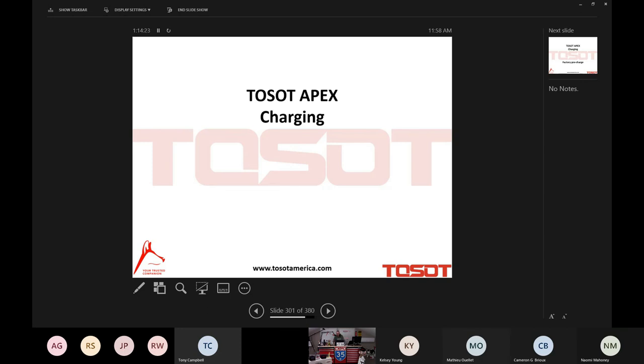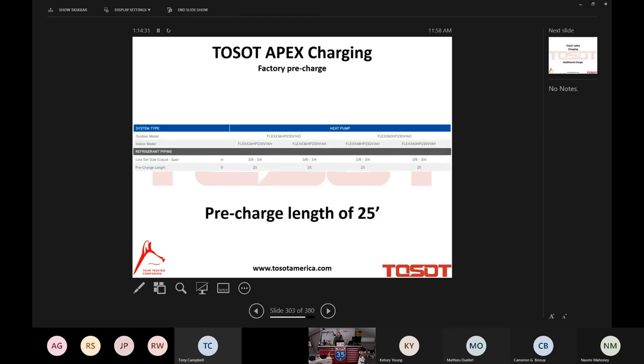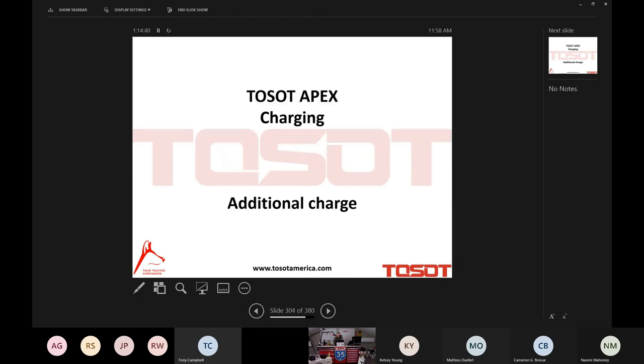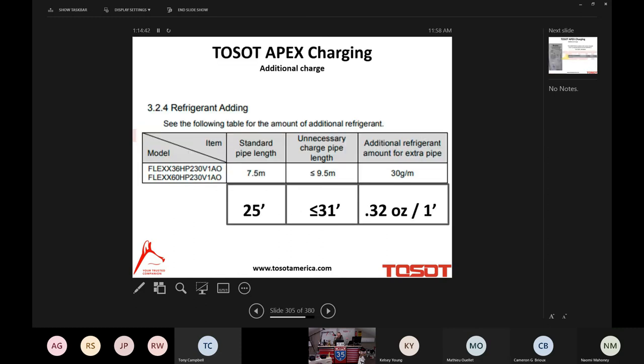Absolutely. Okay, guys, charging. And again, I promise you, we're in the home stretch here. I'm going to run a little late, so I'll do it as quickly as I can. We are pre-charged out of the box to 25 feet. So the outdoor unit, listen to me now, is pre-charged out of the box to 25 feet. We need to add an additional charge only if we go beyond 31 feet. Why 31? If we're pre-charged to 25, what's the deal? Well, that's if we're utilizing the Apex Indoor unit.